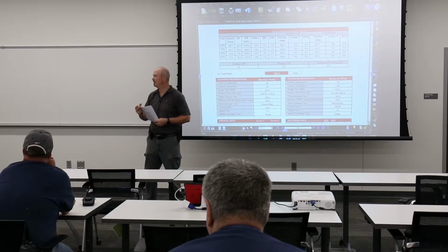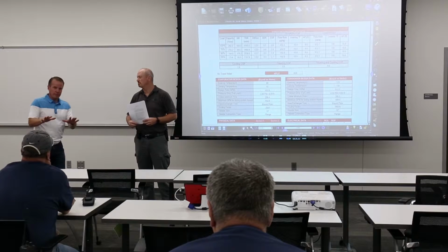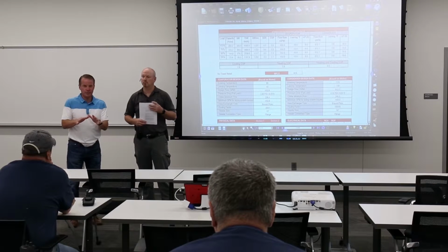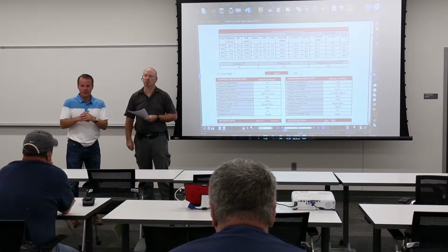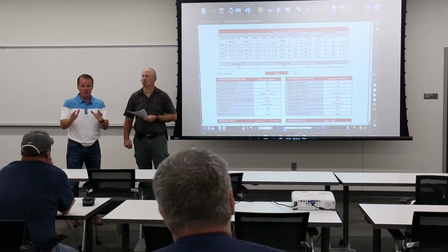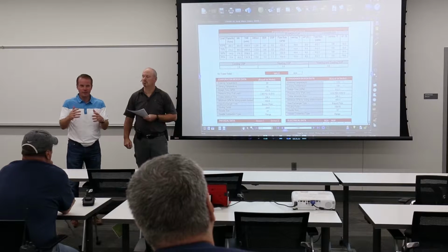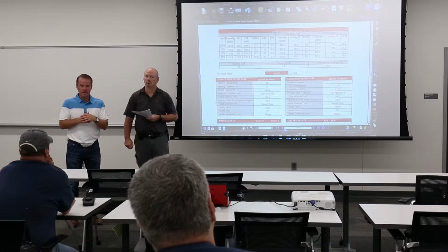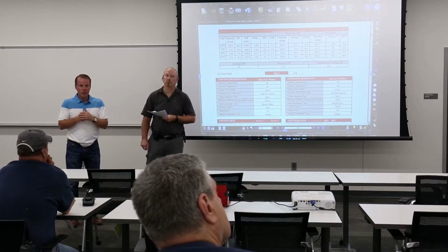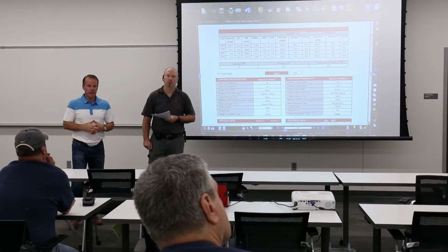Make sure everybody knows. Does everybody know why we have a multi-stack chiller? Why we have a chiller in this building? Do we know why that's there? Because you have campus chilled water. Does that puzzle you on why we have a chiller here? Most of it's because of the shoulder type areas when cooling's not available. That's right.